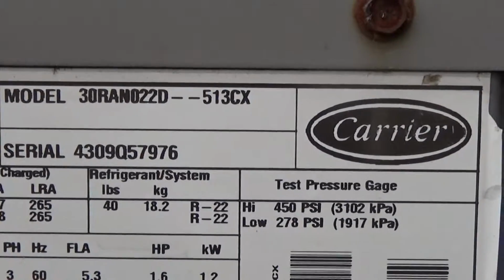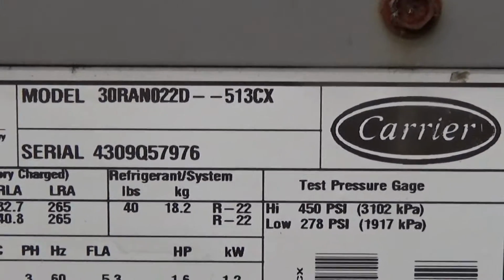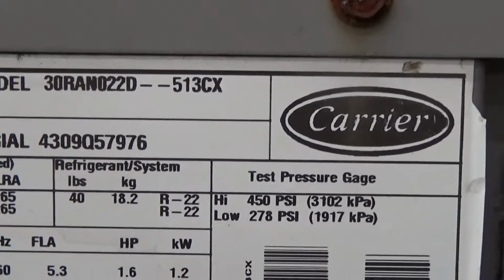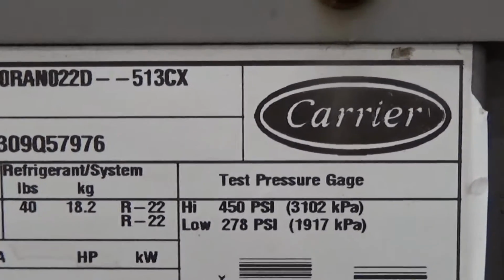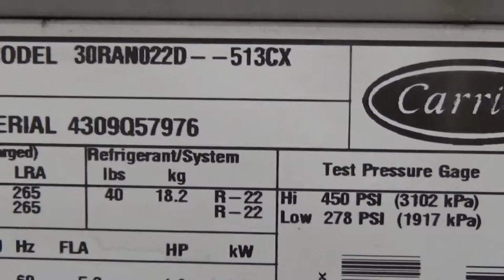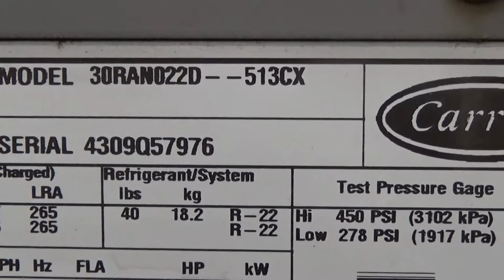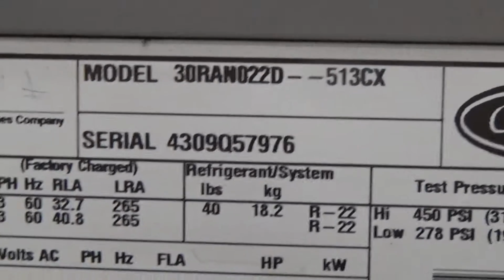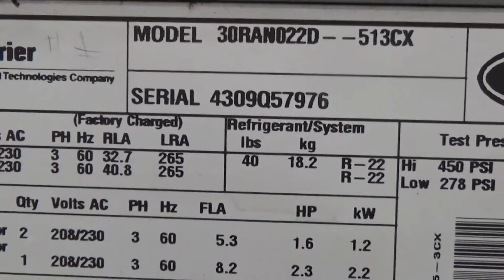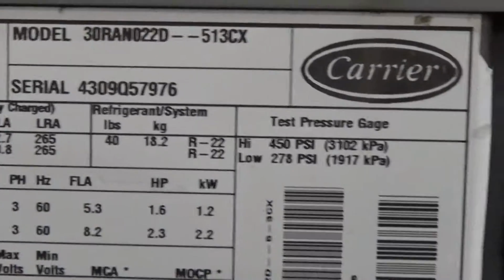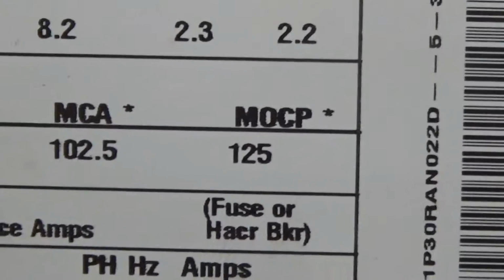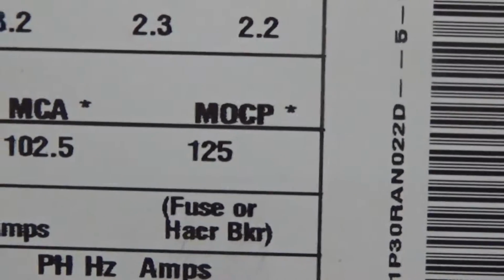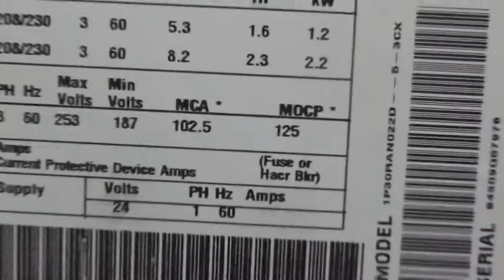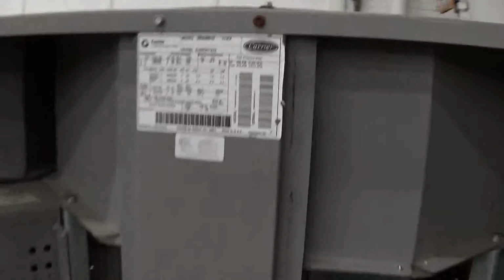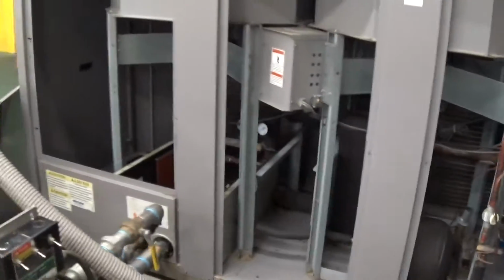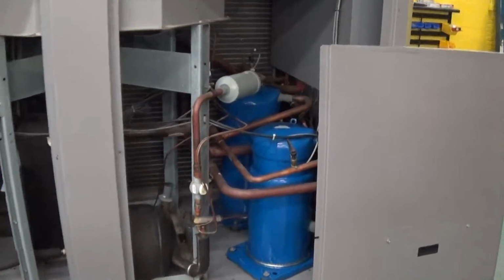This unit's model 30RAN 022 D as in David 513CX, serial number 4309Q57976, and this is a 208/230 volt 3-phase system. Recommended maximum overcurrent protection or maximum breaker of 125. This is just going to be our first video, kind of a static video. We have all the covers off just to show the inside of the unit.